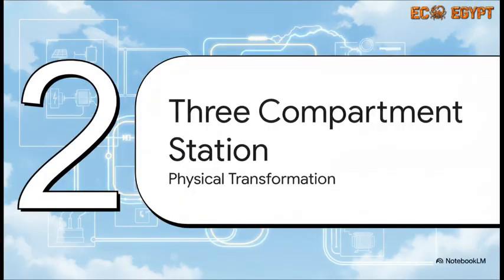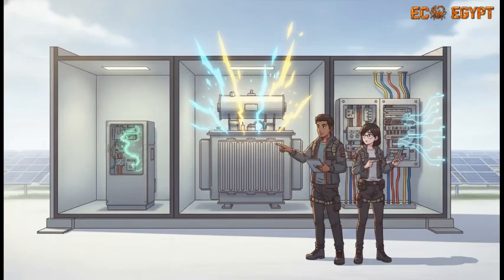Moving right along to Section 2, the three-compartment station. Okay, so the main thing to grasp here is that out in the solar field, the actual power transformation happens inside what we call a three-compartment station. Honestly, the easiest way to think about this is just picturing a transformer station as having three totally distinct but connected rooms. First up, you have the RMU, or ring main unit. This is your compact SF6 gas-insulated switchgear that handles loop switching and transformer protection.